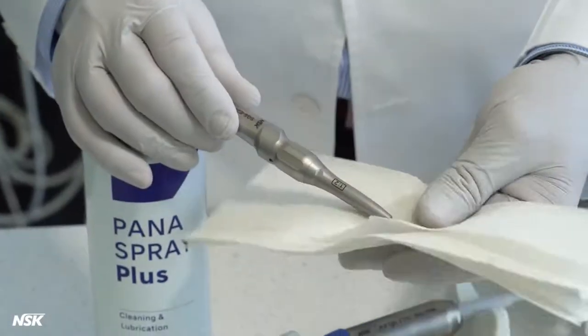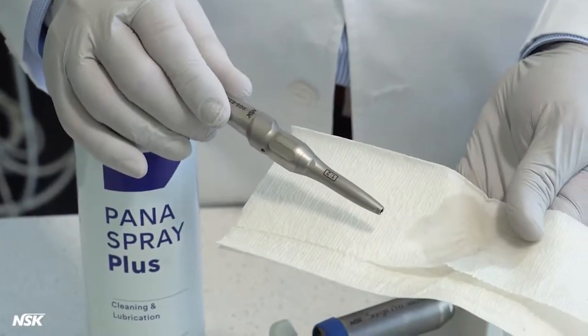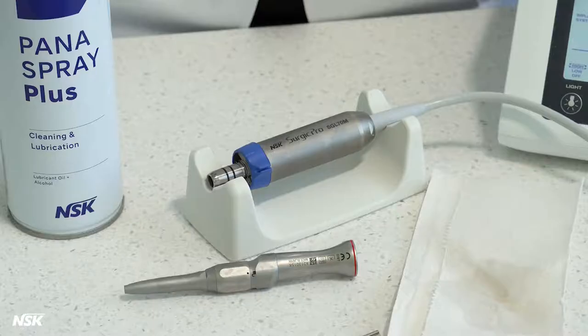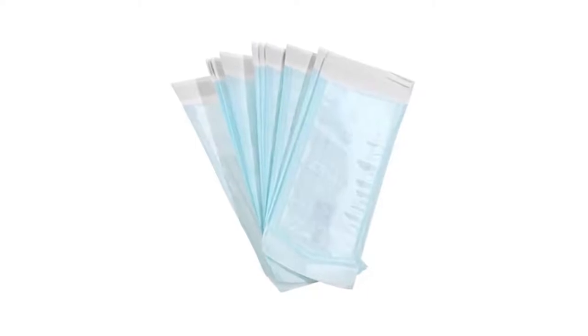The attachment is ready now to be autoclaved using the FDA-approved pouch. The entire motor and its cord are autoclavable. To disconnect the motor cord, pull back the metal sleeve and pull out the cord. Place the attachment and the micromotor in separate autoclave pouches and seal them before putting into autoclave.